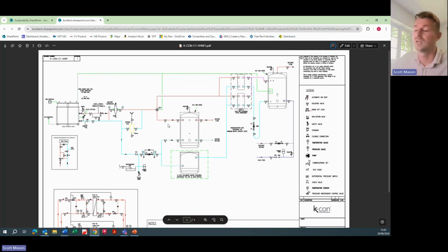So quite a traditional setup, heating and hot water. Some people like this arrangement, some people don't. Again, site specific, budget constraints, etc. 3-port valves are a mechanical thing. They'll only turn so many times. So if that fails, obviously you'll end up with either a cold hot water tank or a hot heating tank. So that's a consideration to make, but it just means you've got a fault on an item that needs replacing. Sometimes people don't like the idea of the heating circuit being diverted away for a long period of time because it's going into hot water mode quite frequently, which is also fair.